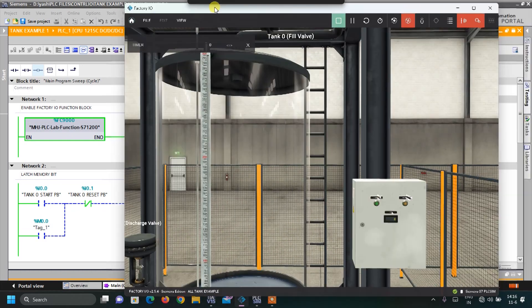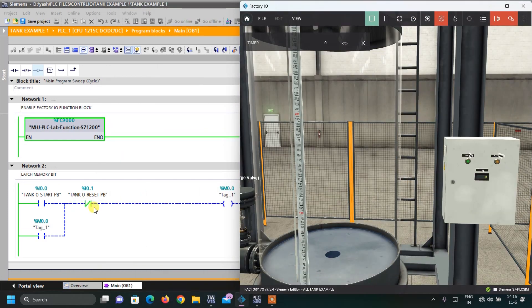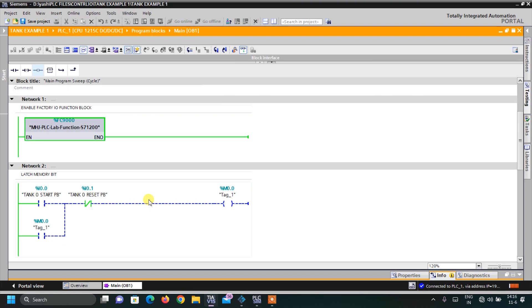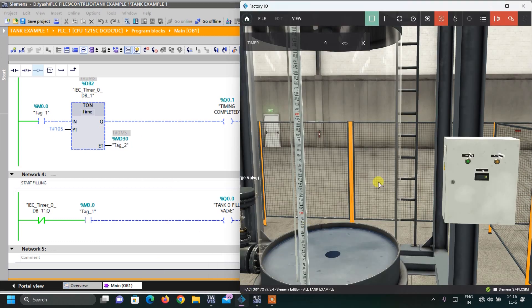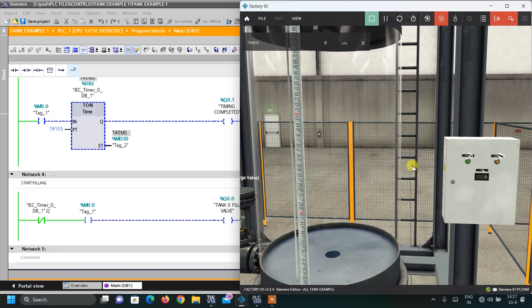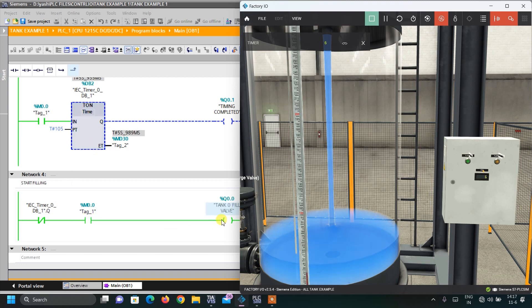Here is the ladder logic. First is a simple latching circuit: pressing the start button latches bit M0, and pressing the reset button unlatches it. In the next network, as soon as start is pressed, M0 triggers an on-delay timer. I have taken the NC (normally closed) bit of the timer — so while the system is on and timing is not completed, the filling valve turns on. When timing completes, the NC bit opens and the valve turns off.